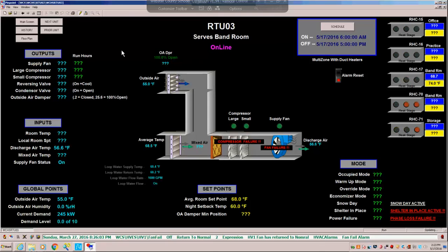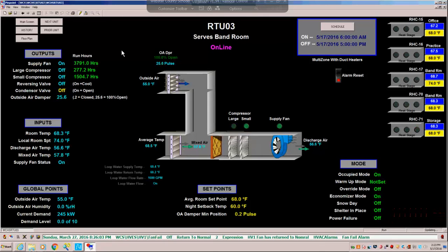If you have graphics that people mess with all the time and disable things, this is a quick visual indication so you don't have to go back into the list views to see what is disabled and what is not. If you keep this consistent, if these were all yellow enabled, I know that is an enabled point.